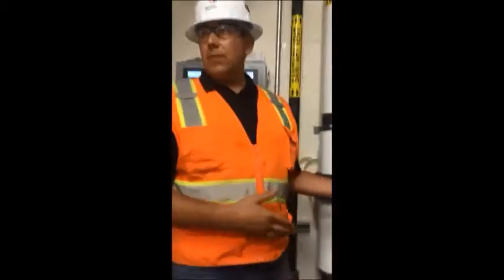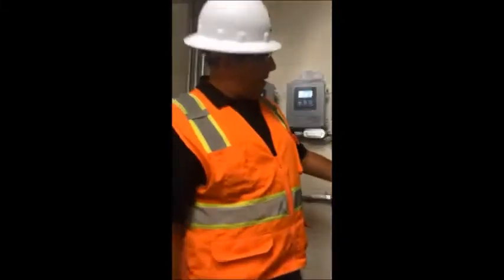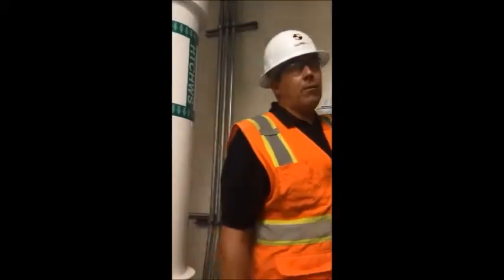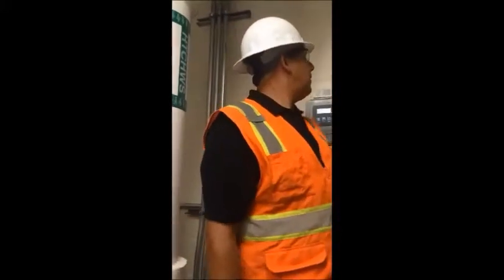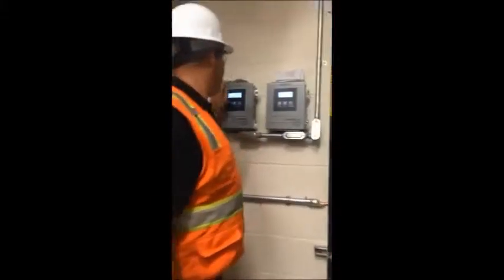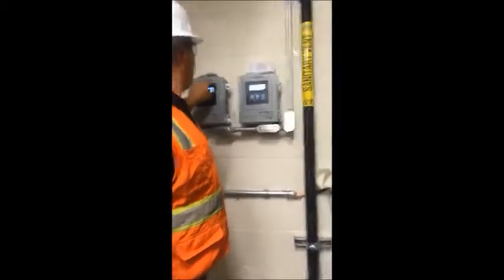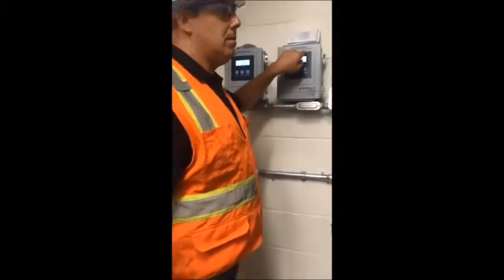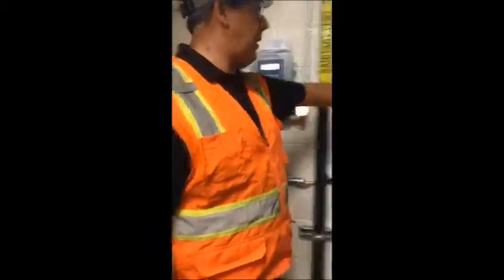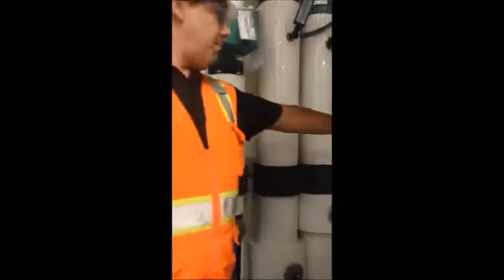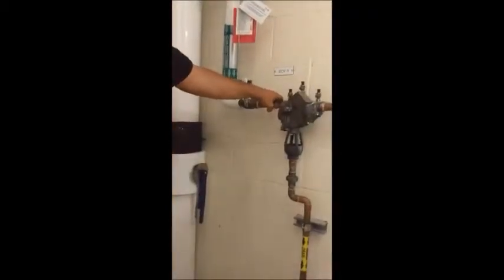So these are our services that come in for chilled water. These lines are for heating hot water and chilled water. And obviously they put a mark, the heating hot water supply and return BTU meter, as well as the campus heating hot water BTU meter and chilled water BTU meter. And then this is for the hydronic side. And then also you have your makeup with a backflow preventer. The backflow preventer feeds up. You have pressure reducing valves for the hydronic side, one for chilled water and one for heating hot water. Okay.